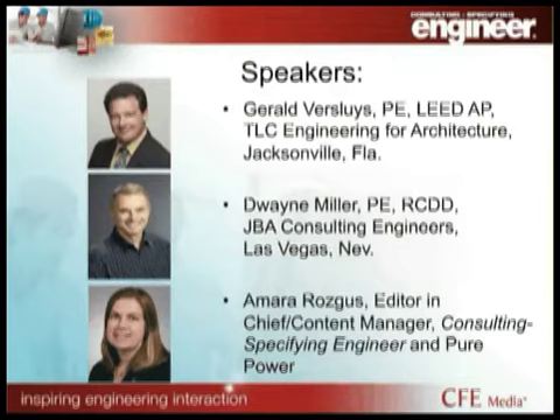That gets interesting because now you're going to be generating into the, well, it depends on how it's structured. We've done it for hospitals in Southern California. Everybody probably remembers when the rolling blackouts were occurring. One of our clients would actually get an alarm from the utility, and they would transfer a lot of their load to their on-site generation. So there's a couple of things to talk about. If you're talking about load shedding the grid and taking your load off the grid to free up capacity, we've seen that as an option.